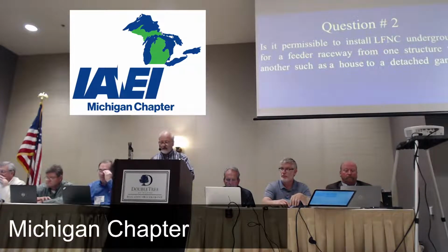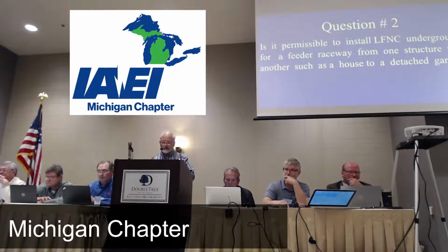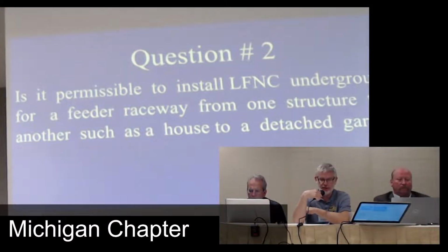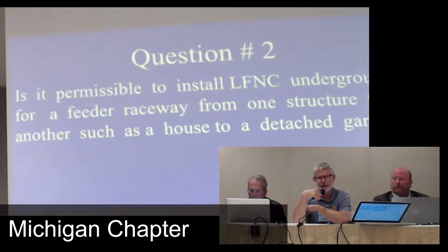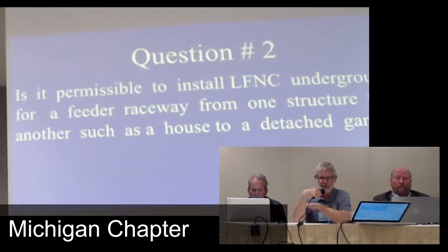Okay, for Dan. Is it permissible to install LFNC underground for a feeder raceway from one structure to another, such as a house to a detached garage? Looking in the code under 356, which is the liquid flexible non-metallic conduit, use is permitted. 356.10(4) says if it's listed and marked for direct burial, you can use that specific raceway for that. You look through a few of the other ones down there, the use is permitted. It can be longer than 6 foot if need be, as long as it's secured and supported properly. So the answer to that would be yes, it's allowed.